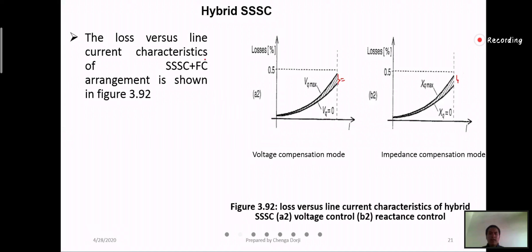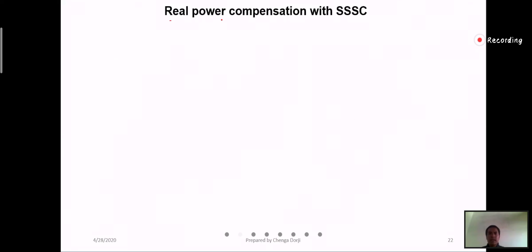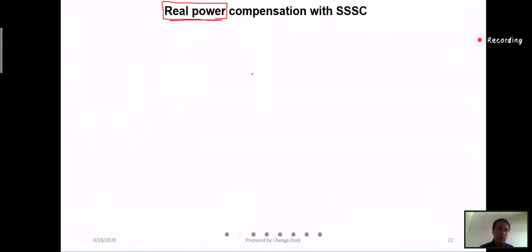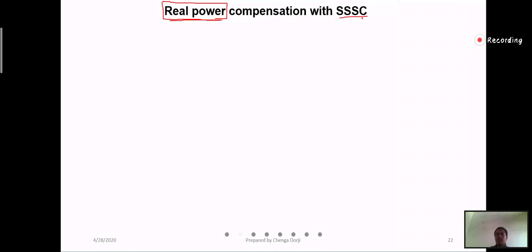Another feature of SSSC is that it can be used to exchange real power with the AC system, in addition to reactive power. All shunt compensation devices were able to exchange only reactive power. When it comes to the exchange of active power, they were not able to do so — except for STATCOM, but it was not that effective. So real power compensation by SSSC is effective, and this is the main feature of SSSC.